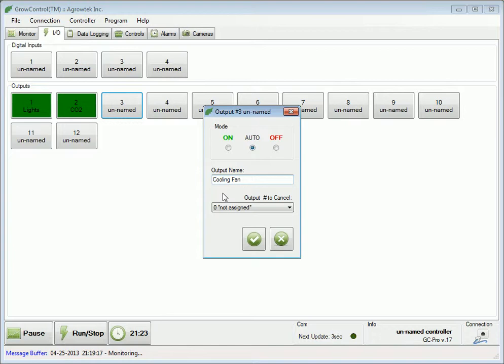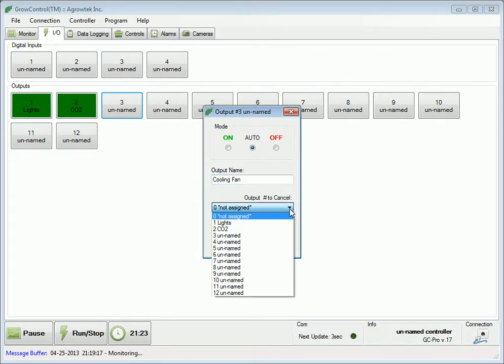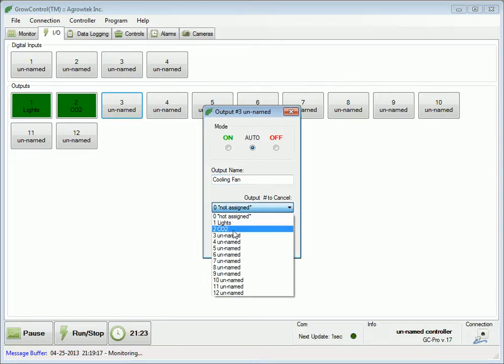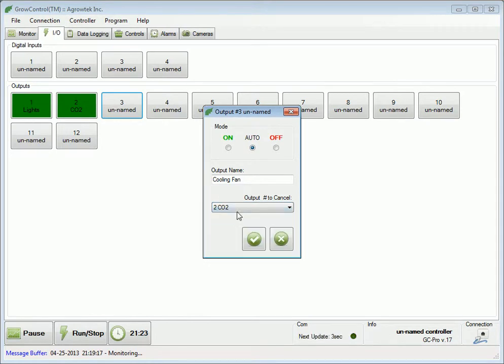In this application, we're going to use this cooling fan to bring in fresh outside air, so we want the CO2 output to be turned off whenever this cooling fan output is on. To do this, we select an output to cancel — we'll cancel the CO2 output whenever this cooling fan output is on. Let's press the check mark to send these settings to the controller's memory.